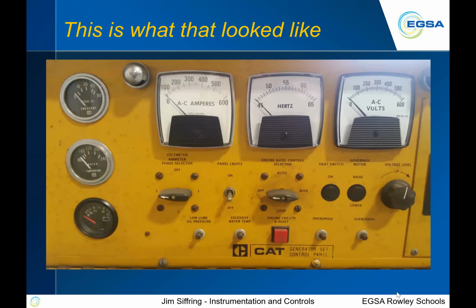So what does that look like? This is just an old Cat panel. I think this is what they used to call the Redcos, but it does everything we're talking about here. On the left, you've got an engine oil pressure and a coolant temperature. On the very lower line, there's a low lube oil pressure, excessive water temp, an overspeed and an overcrank. Those are all trip devices, and if they trip, they light up. You've got a reset button between them.